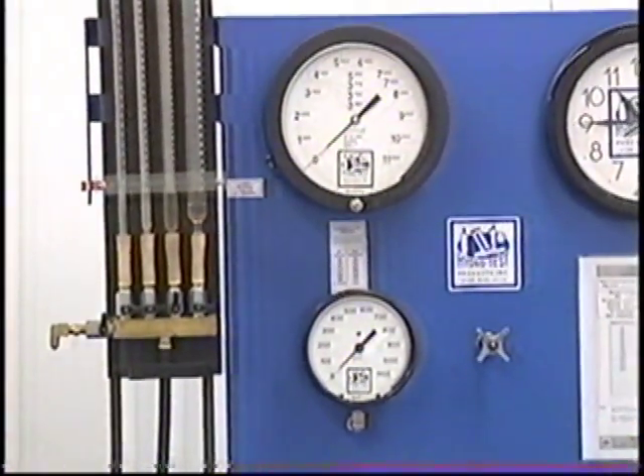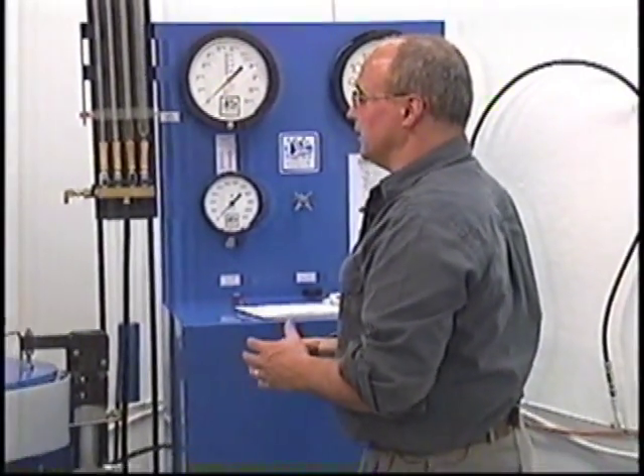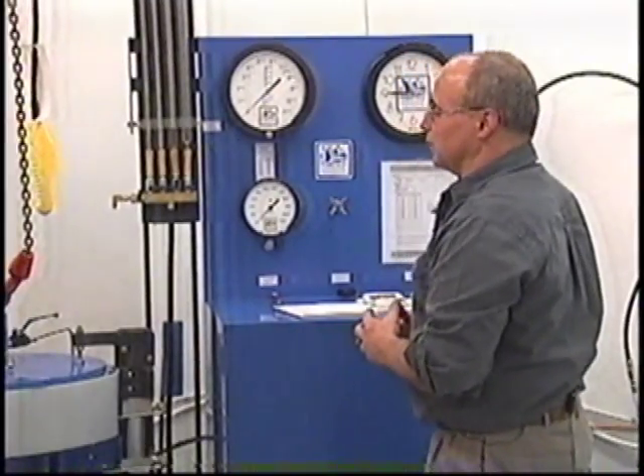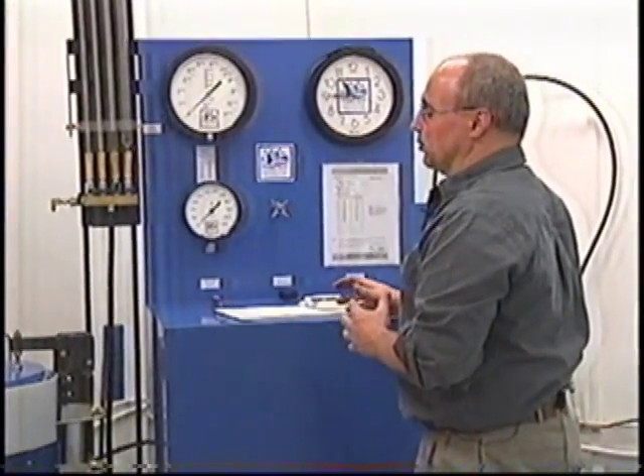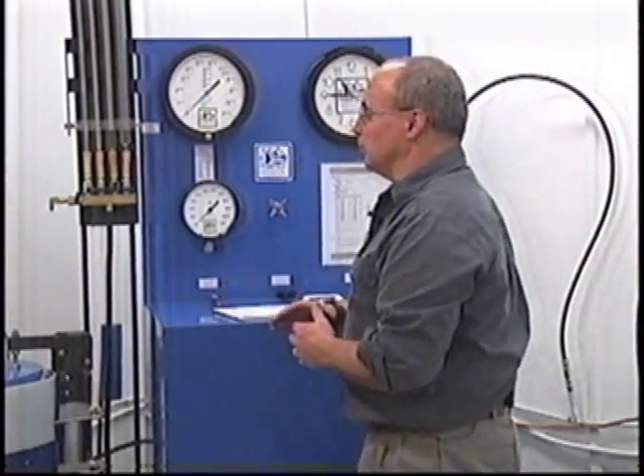Since you've taken that hose off of the water jacket lid, you've isolated everything to a low pressure side. So it cannot be anything to do with the actual hydrostatic test console or the pump. It would either be the valve or a temperature problem.